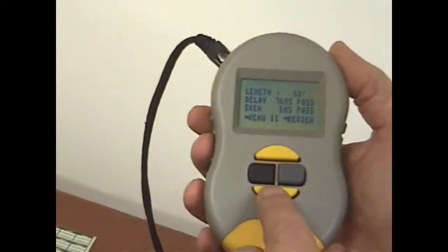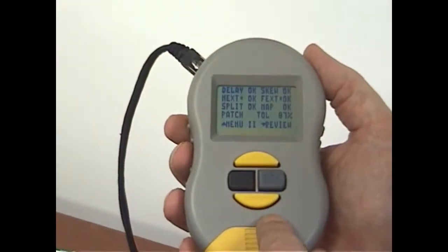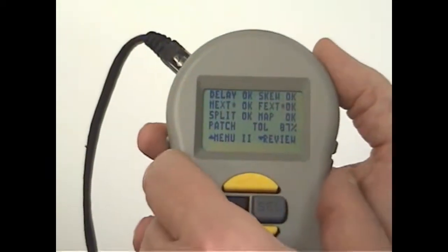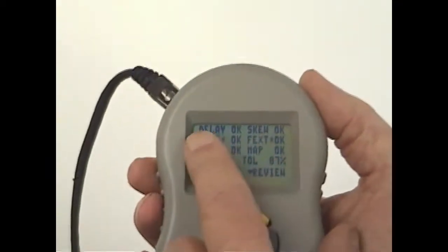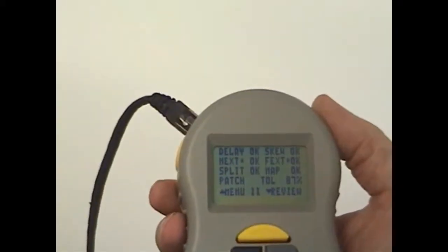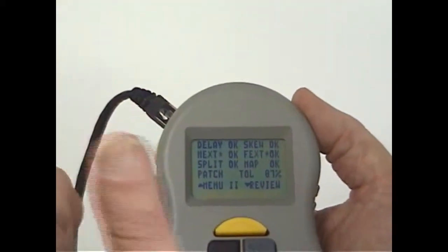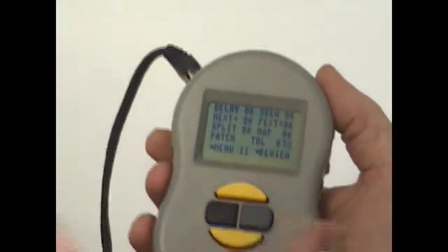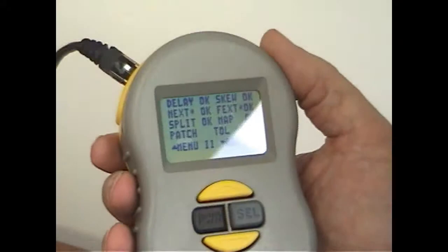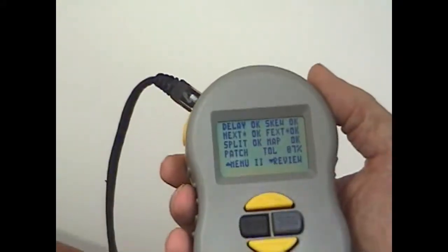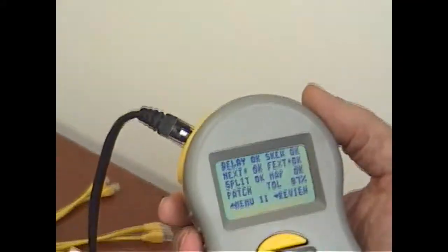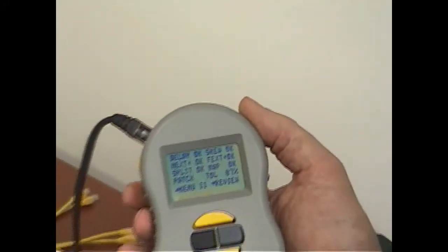Now let's continue with our review. Here is a summary of all the tests performed. The delay, which is the time it takes data to travel from one end of the cable to the other, is okay. The skew, the difference in delay between pairs, matters because data is sent on several pairs at the same time, and it all has to arrive at the receiving unit together—if there's too much difference in time...